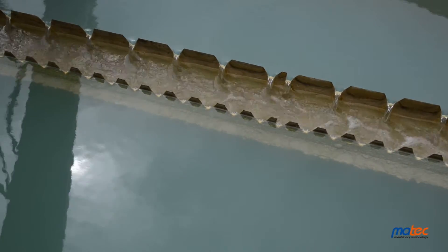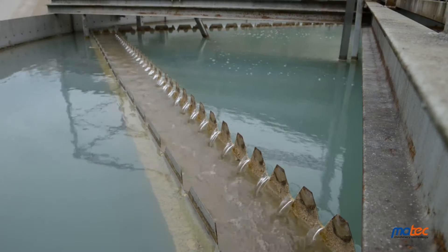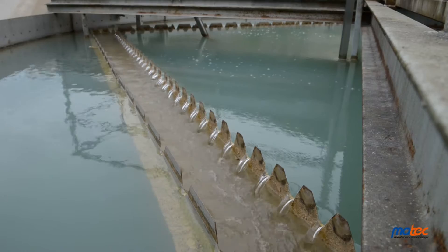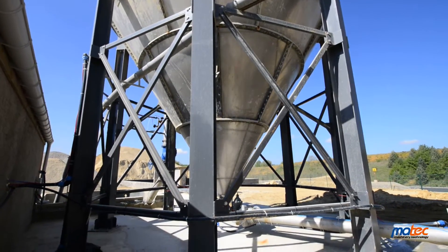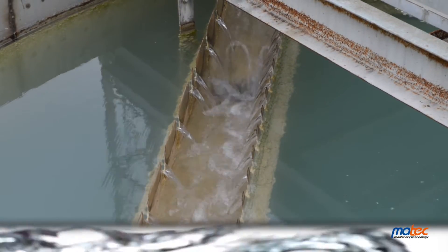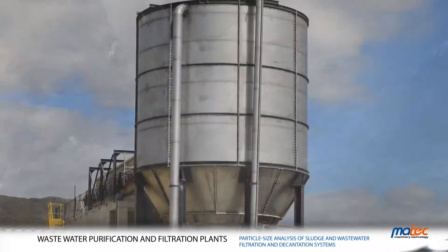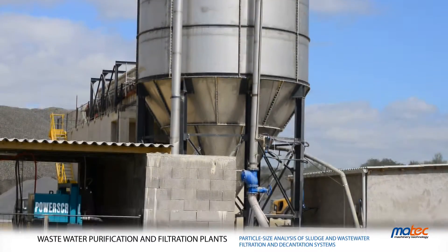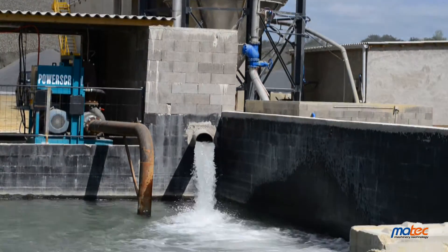Water reaches the silo through the countercone on top and it is clarified. Slurry, thanks to the polyelectrolyte action, becomes heavier, separates from water and settles at the bottom, while clarified water goes up and overflows into the drainage gutter to end in the clarified water tank. Water treated by MATEC decanters is purified and ready to be reused.